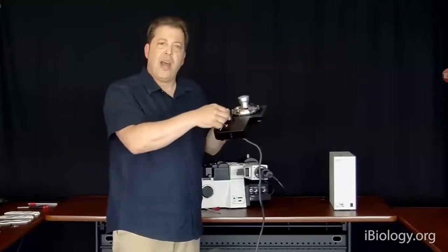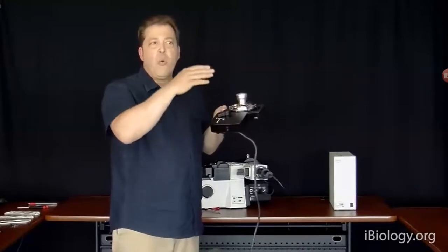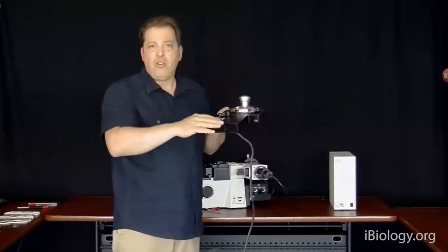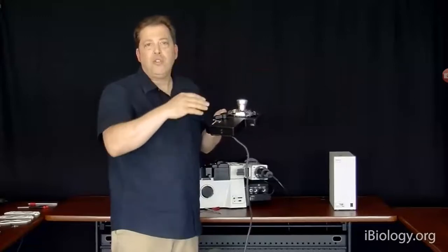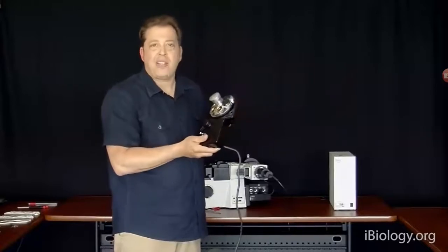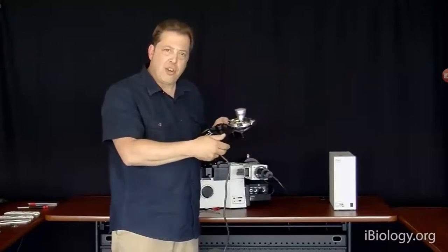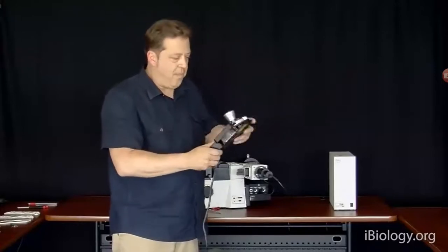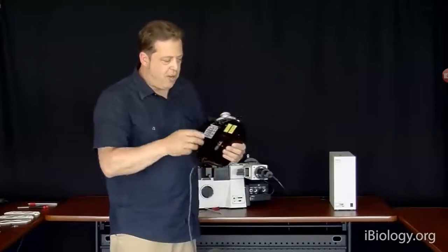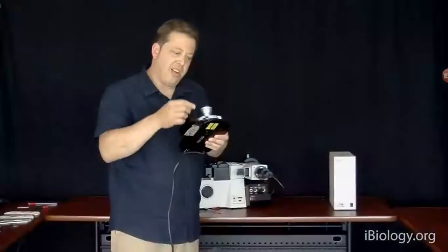just showed you, and goes to a linear CCD array that actually knows whether the scope is in focus, whether it's drifting below due to gravity, or whether it's drifting upwards due to thermal expansion of the materials, and it tracks that, and it does it every 5 milliseconds. So it's imperceptible to the user, but it'll hold focus indefinitely. And basically that's all there is really to this component. It's got slots here for your prisms for differential interference contrast.